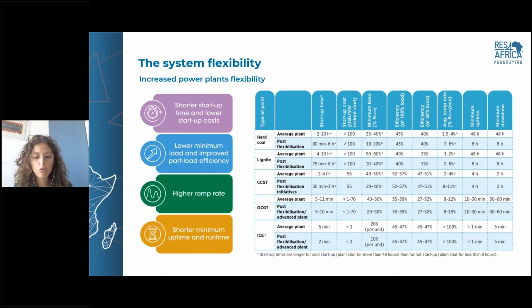Here is an example of what we intend with increasing the flexibility of the plants. It means, for example, shortening the startup time and lowering the startup cost. Decreasing the minimum load of the plants and improving the partial load efficiency, because the problem is that conventional plants have low partial load efficiency. So improving this may help, being able to reduce the minimum load. Increasing the ramp rate and having shorter minimum uptime and runtime.